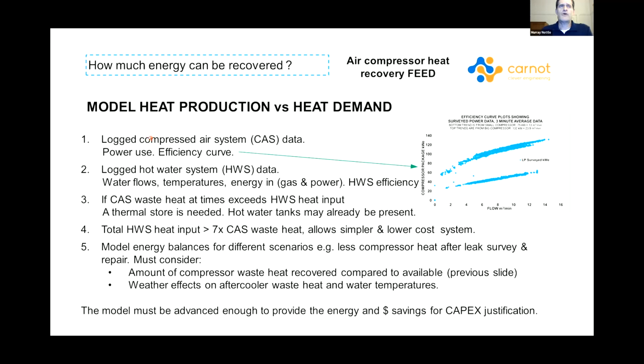So how much energy can be recovered? You've got to log what your compressed air system's doing. You know how much power is going into the compressor, and that will give you an efficiency curve like you can see here. You've got to log your hot water system, so you know what your water flows and temperatures are, and what your energy is in terms of gas and power. This will also pick up the mismatch between when your heat's being generated and when you're using it, and whether you're going to need hot water tanks. If your hot water system demand is much bigger than the compressed air heat output, you can go with a simpler design for a heat recovery system. So you need to be aware of all of that when you're trying to design your system.